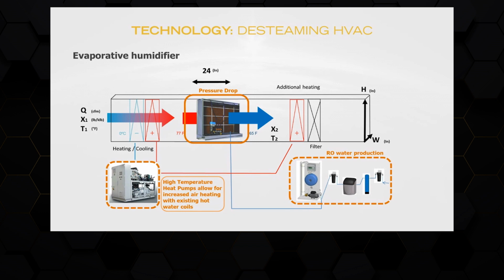Adiabatic process, as we know, is a natural and extremely efficient process. An adiabatic humidifier converts liquid water to water vapor by using the adiabatic process. Dry air is passed through a corrugated wet bank of cell media, which is made of non-organic wet fibers. So the humidifier uses sensible heat in air to evaporate water, which cools and humidifies the air. The adiabatic process consumes no electricity, making it an ideal choice to reduce energy and carbon footprint.